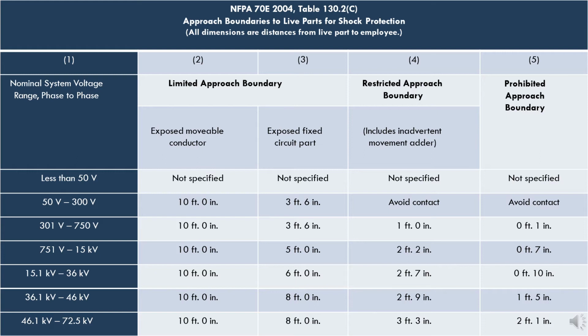When looking at where the different boundaries start in relation to energized electrical circuits, we first try to figure out what voltage we're dealing with. In this example, the greatest voltage we'll be exposed to is 13.2 kilovolts. So we look at column 1 and find where that falls, which is between 751 volts and 15 kilovolts.